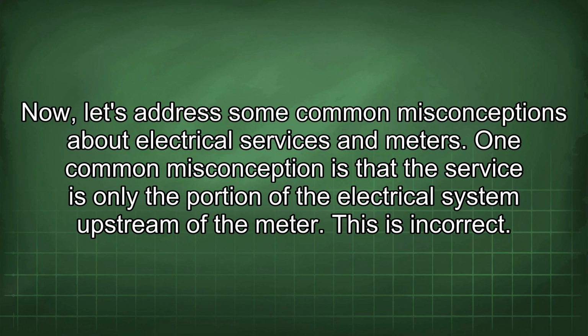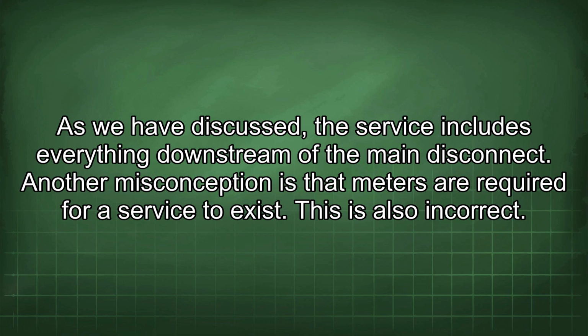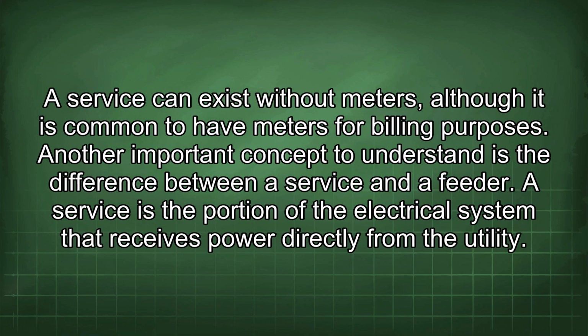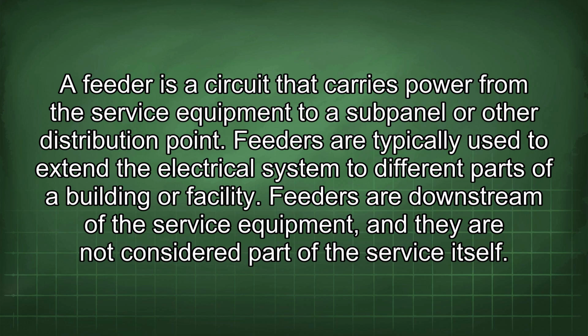One common misconception is that the service is only the portion of the electrical system upstream of the meter. This is incorrect. As we have discussed, the service includes everything downstream of the main disconnect. Another misconception is that meters are required for a service to exist. This is also incorrect. A service can exist without meters, although it is common to have meters for billing purposes. Another important concept to understand is the difference between a service and a feeder. A service is the portion of the electrical system that receives power directly from the utility. A feeder is a circuit that carries power from the service equipment to a subpanel or other distribution point.